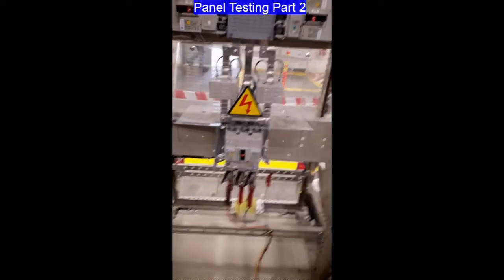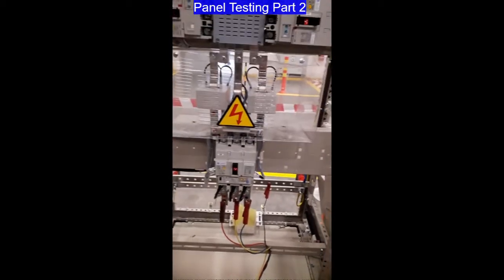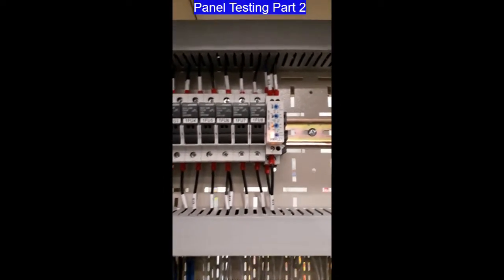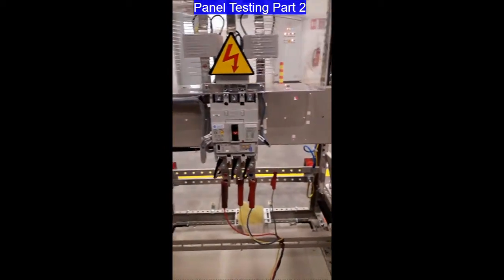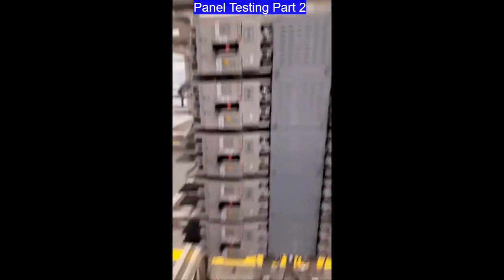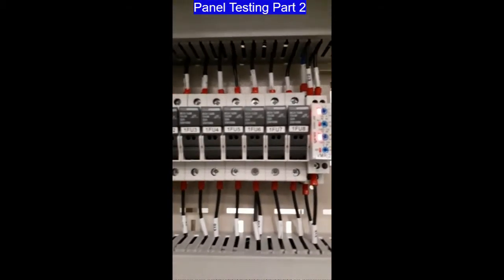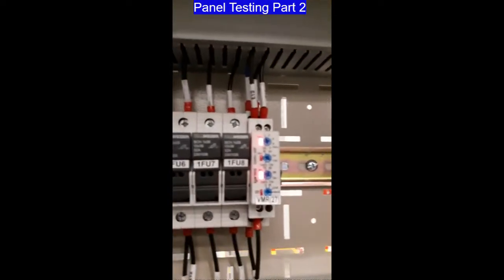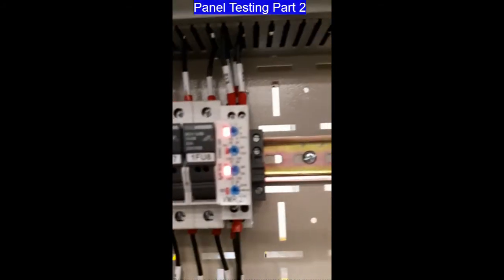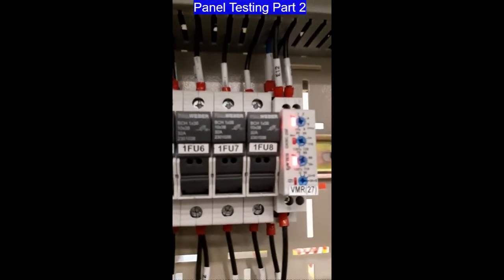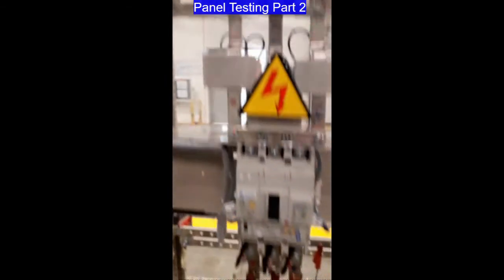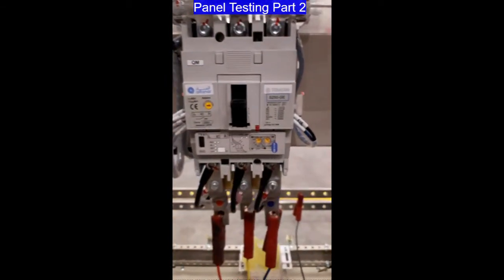All right, now we are going to continue with the phase failure test of the voltage monitoring relay. Our monitoring relay is healthy now. Right over here, we are going to make a failure of at least one phase. Can you please make the failure? Once there's a voltage failure, you will find the signal indication lamp on our voltage monitoring relay, and the main breaker also trips. It's already in trip status.